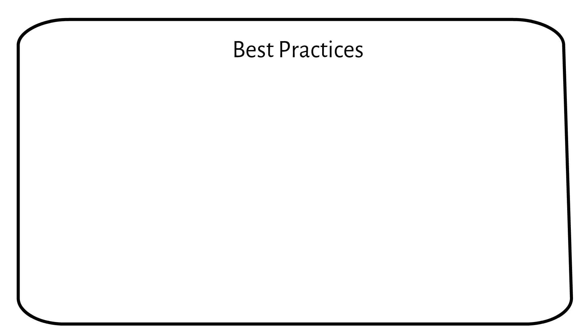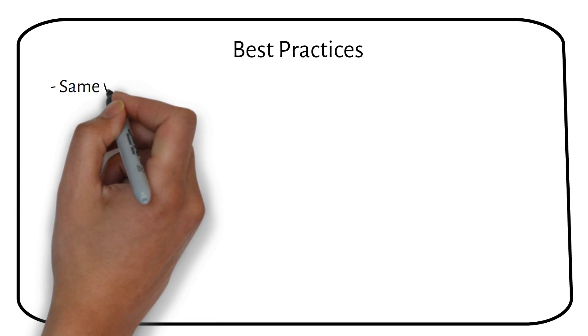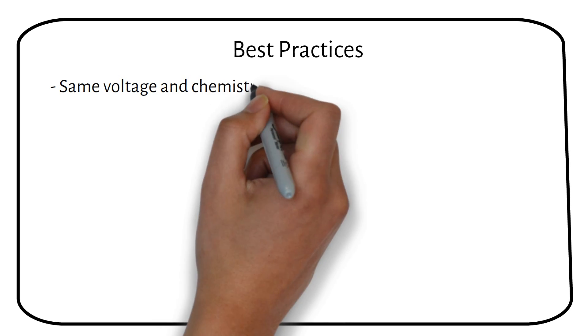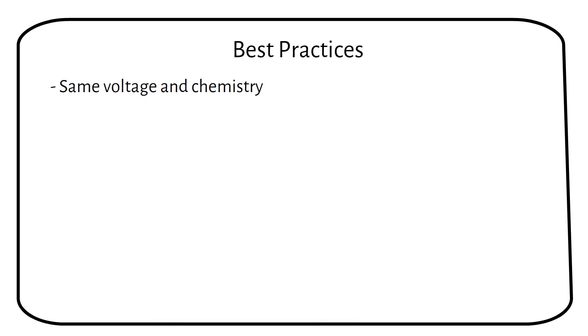Wiring batteries in parallel might seem easy, but there are best practices that need to be followed. Firstly you should use batteries of the same voltage and chemistry. If you use lead acid batteries, you should use batteries of the same age. This doesn't matter much for lithium, because they degrade much slower.